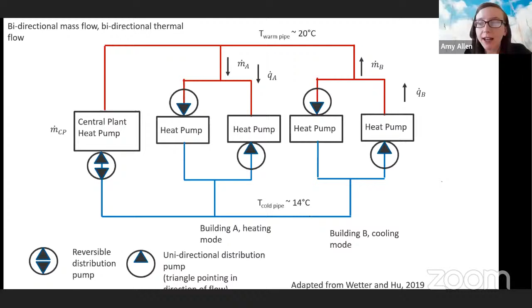This diagram shows an alternate configuration of a 5G DHC system in which a single pipe serves the entire network and through which water is circulated, which is used for both heating and cooling. And in this case, if inlets and outlets for the connected loads are located close together, there's a minimal or negligible pressure differential across each connected load, which allows them to be hydraulically decoupled from the main loop and can mitigate the potential pressure control instabilities at low load conditions.